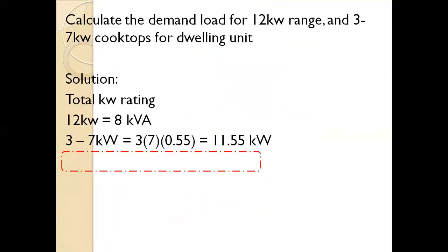Then we also have another problem. Calculate the demand load for a 12 kilowatt range and 7 kilowatt cooktops for dwelling units. Apply column C and column B. We have one 12 kilowatt range, so its total demand is 8 kVA. Then three 7 kilowatt, so 3 times 7 times the multiplying factor, for a total of 11.55 kilowatt. So its demand is 19.55 kilowatt.